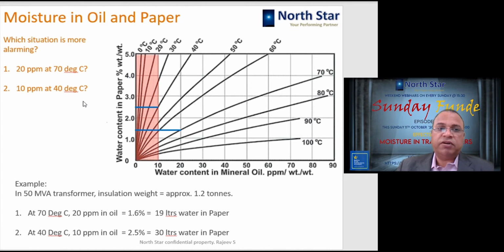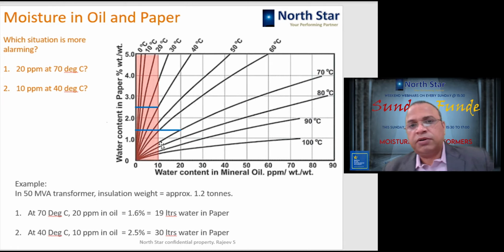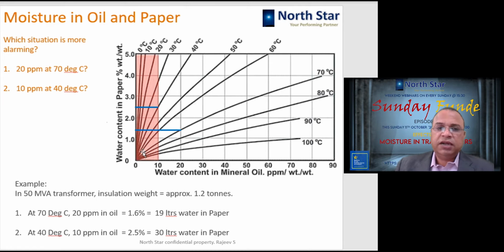Okay, ideally when you are operating a transformer at 40 degrees centigrade, your ppm should be very low, around less than 5. So if a normal transformer which is normally kept around 50 to 55, let us say 60 degrees centigrade, then with this graph we can say the normal ppm level, if we want to keep the transformer in dry condition, less than 0.5% moisture, then the ppm in that oil should be somewhere around 3 to 4 ppm. Just an example, not to be used in real life, but to make the point clear.